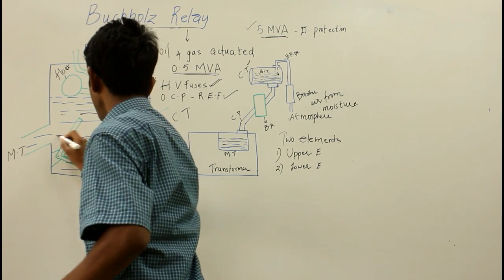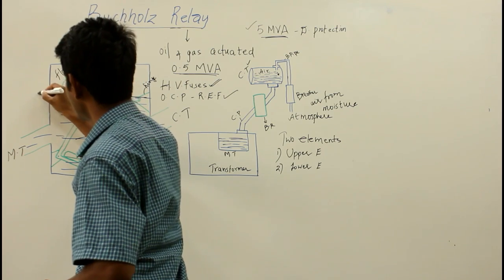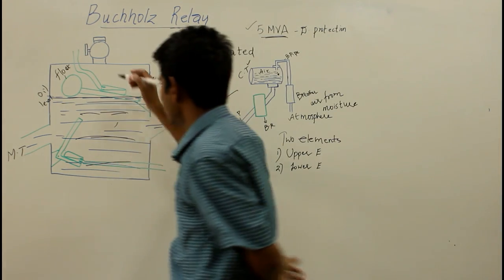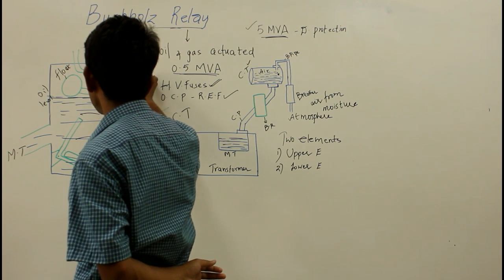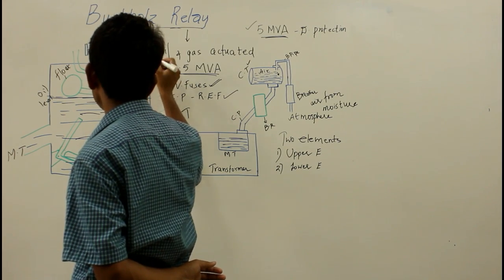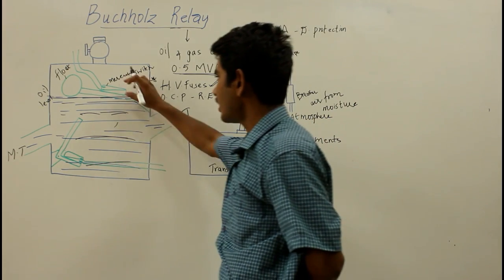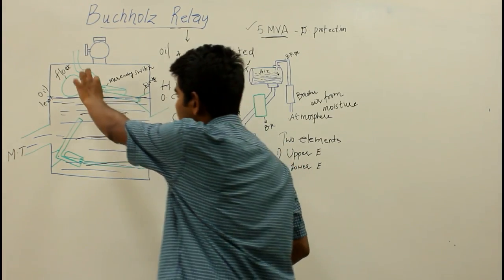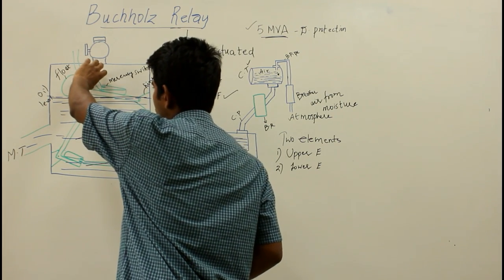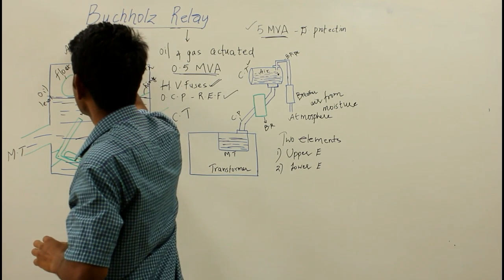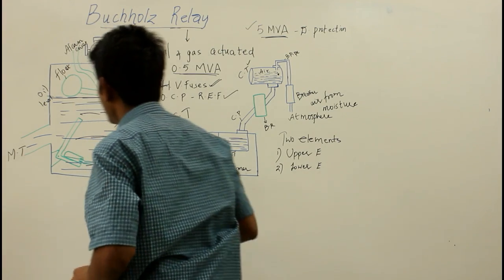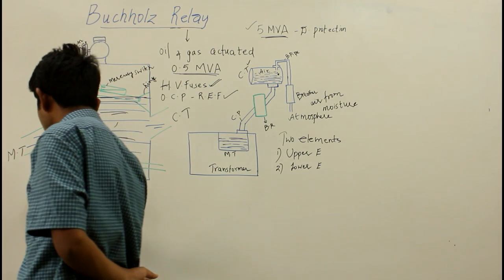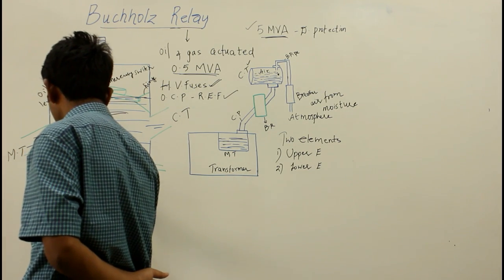Depending on the position of the oil, the float can move up and down. One mercury switch is fixed on the float such that the alignment of the mercury switch depends on the position of the float. If the float goes down, the alignment of the mercury switch also changes. The electrical leads are taken from this mercury switch through a molded terminal block to the alarm circuit. The lower element consists of a baffle plate.